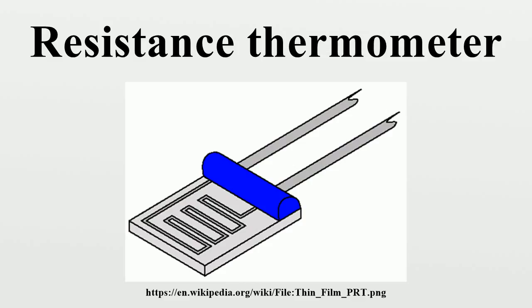Classifications of RTDs. The highest accuracy of all PRTs is the standard platinum resistance thermometers. This accuracy is achieved at the expense of durability and cost. The SPRT's elements are wound from reference-grade platinum wire. Internal lead wires are usually made from platinum, while internal supports are made from quartz or fused silica. The sheaths are usually made from quartz or sometimes Inconel depending on temperature range. Larger diameter platinum wire is used, which drives up the cost and results in a lower resistance for the probe. SPRTs have a wide temperature range and are approximately accurate to plus or minus 0.001 degrees Celsius over the temperature range. SPRTs are only appropriate for laboratory use.